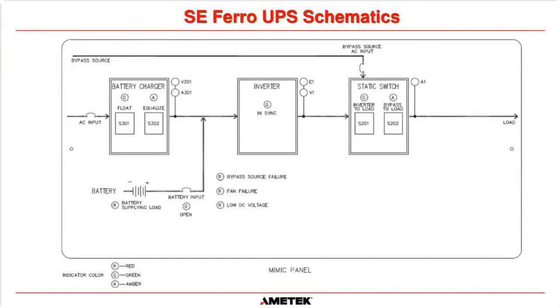And then we have the mimic diagram. This is an exact replica of the front of your UPS. Okay. So once again, on this UPS, it's showing the AC input breaker. We have a float push button and an equalize push button. Okay. And you can see down here, the indicator color: R is red, G is green, and A is amber. So here we're saying that the float lamp is green and that the equalize is amber. There are the two voltmeters and ammeters that we talked about on the block diagram.